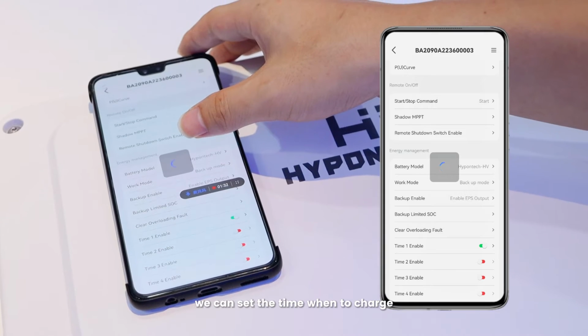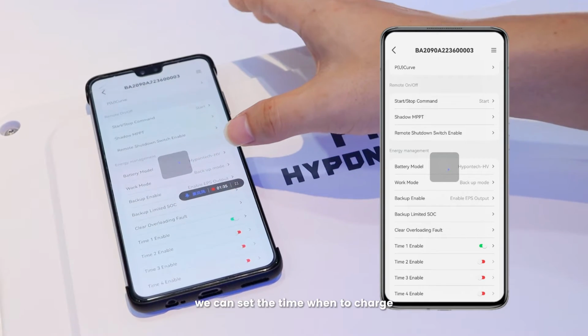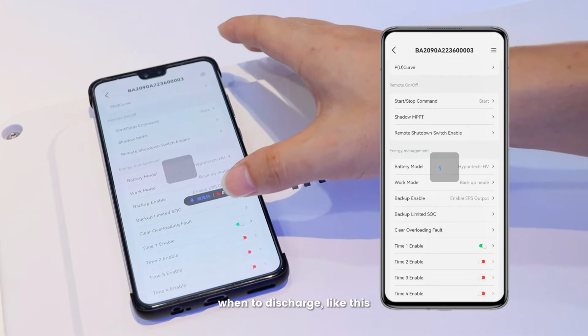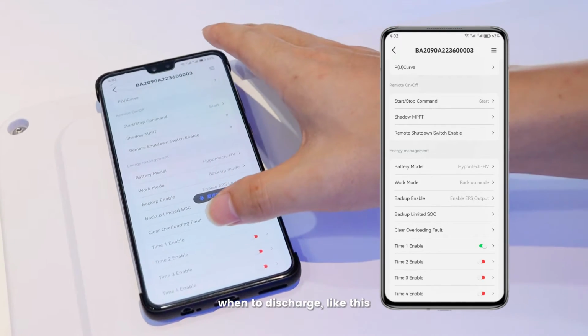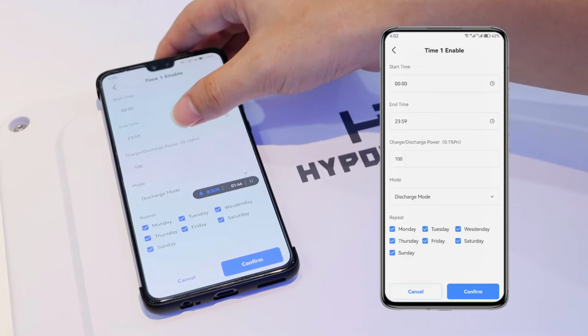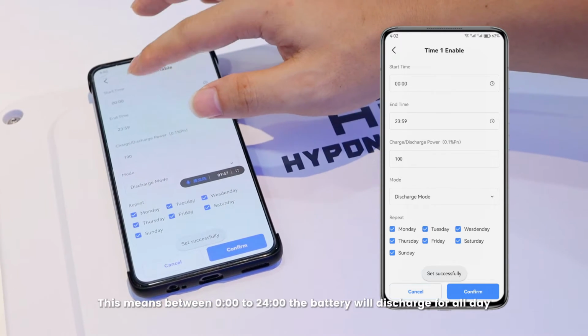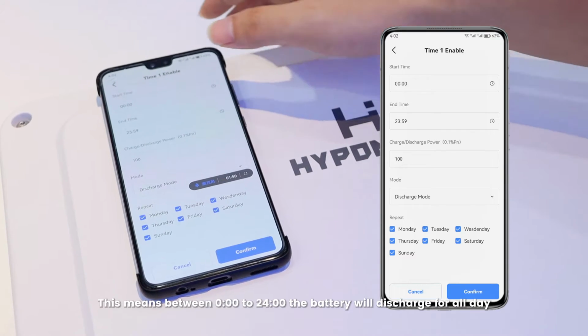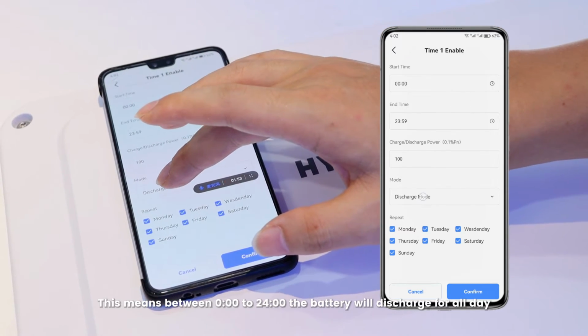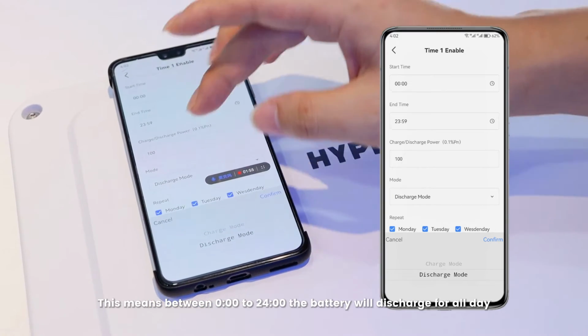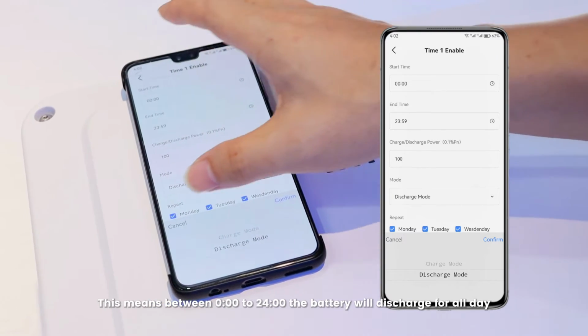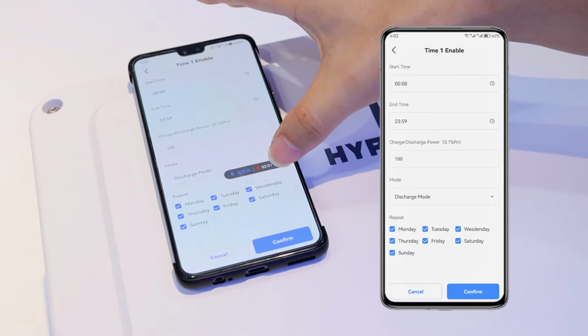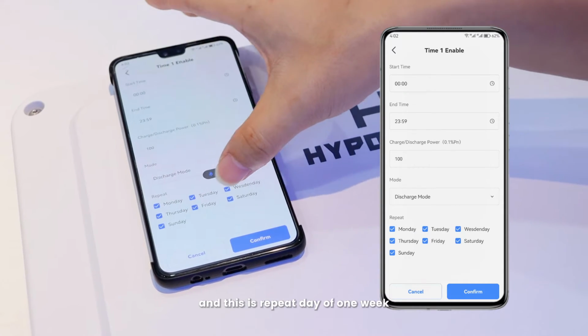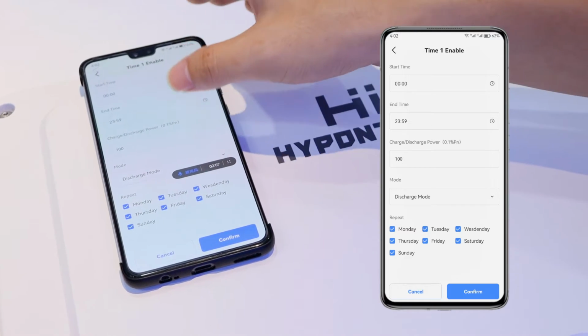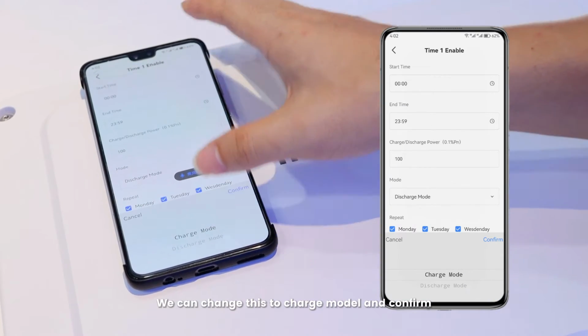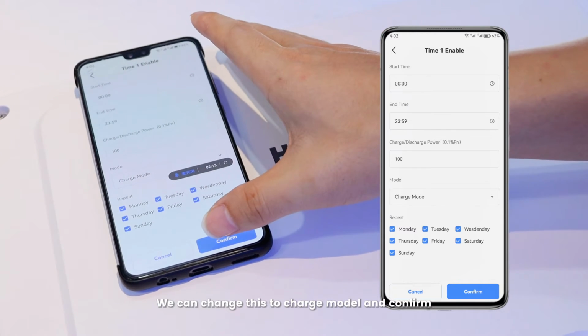After we choose the working mode, we can set the time for when to charge and when to discharge, like this. This means between 0 to 24, the battery will discharge for all day. This is a repeated schedule for each day of the week. We can change this to charge mode and confirm.